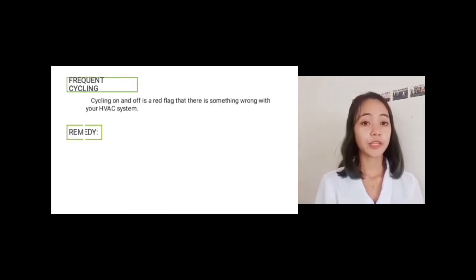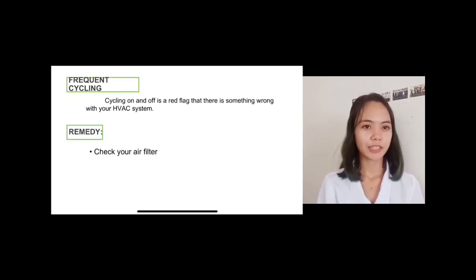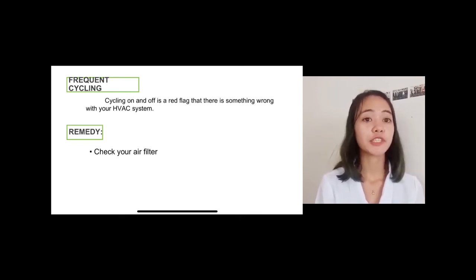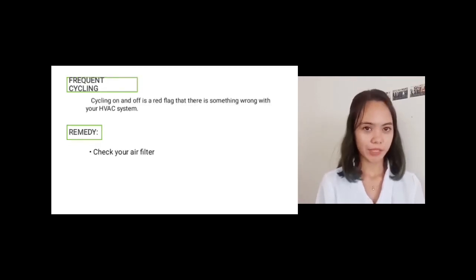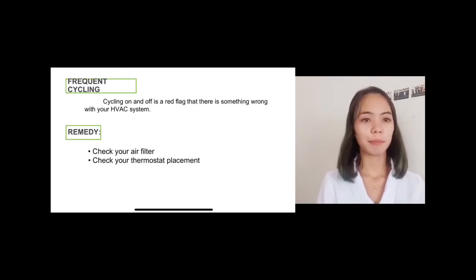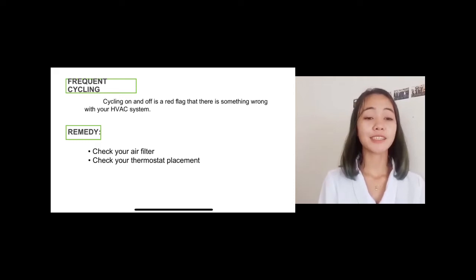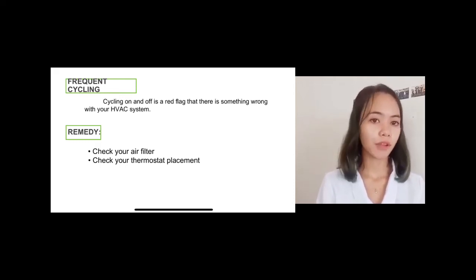A remedy for this would be, first, check your air filter. A clogged air filter can cause a wide variety of air conditioning issues. It's a good idea to check your air filter and change it if it's clogged with dust. Second is check your thermostat placement. Make sure the thermostat isn't too close to the return air register so it doesn't get confused by the influx of cool air and produce the wrong readings.